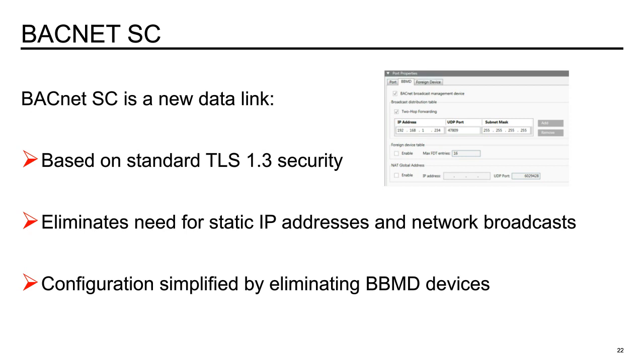Another advantage of BACnet SC is no static IP addresses are required. This reduces the burden on IT groups and may decrease installation and lease costs to users. I had a situation here in Atlanta with a customer. The IT department actually charged for every IP drop that was used, and then in addition to that fee to install it, they also charged a monthly leasing fee. So be aware of that when you're dealing with BACnet IP installations.